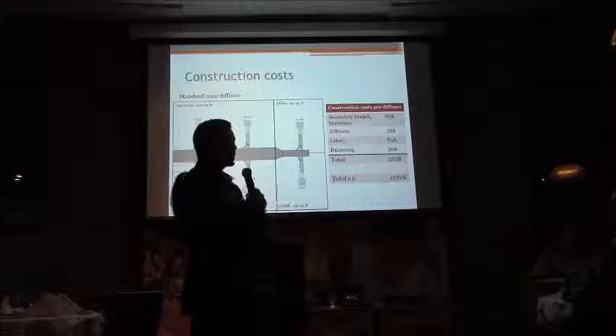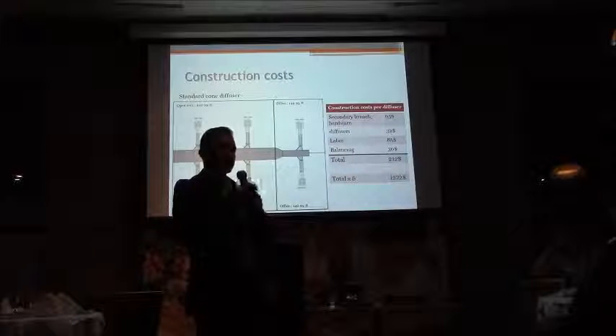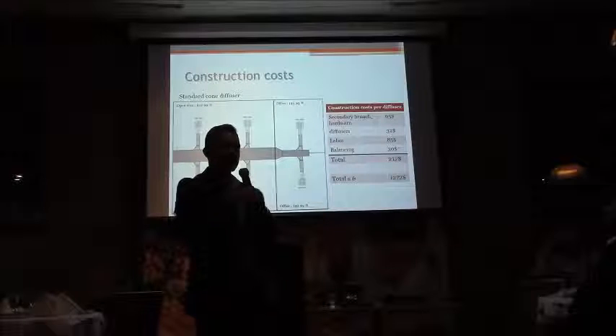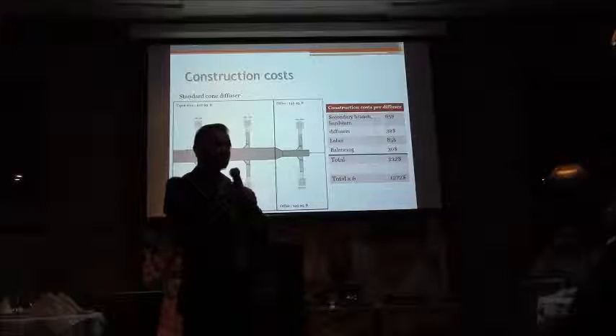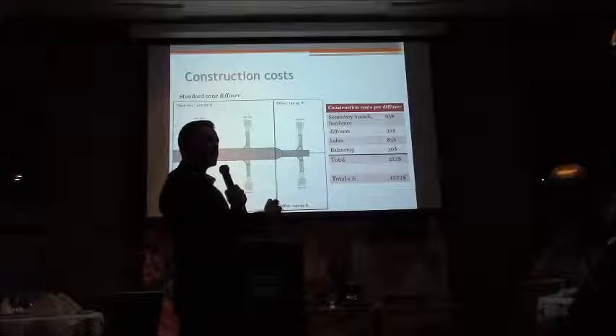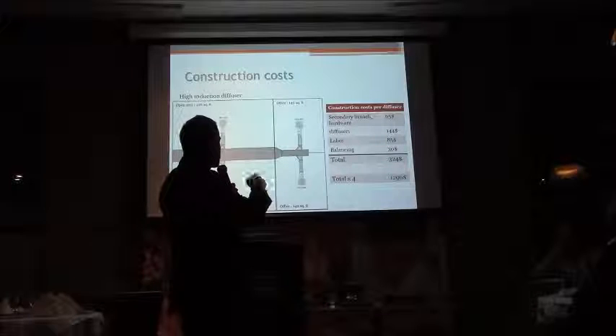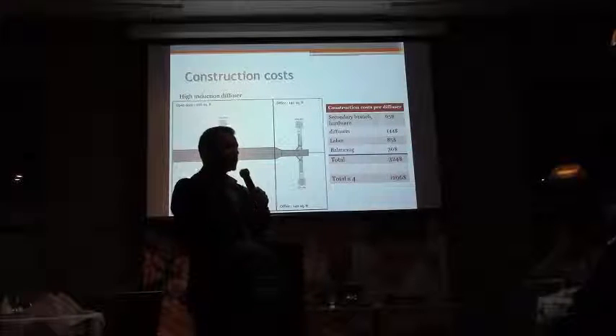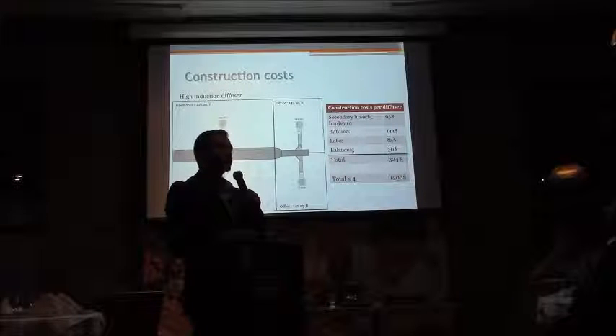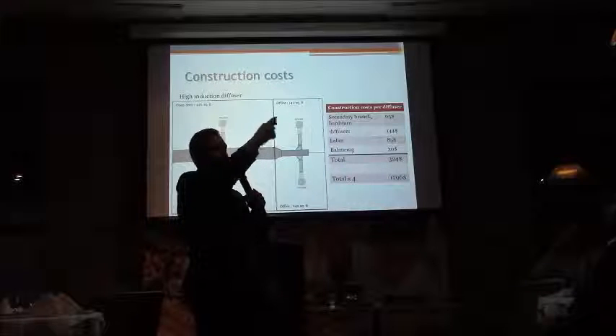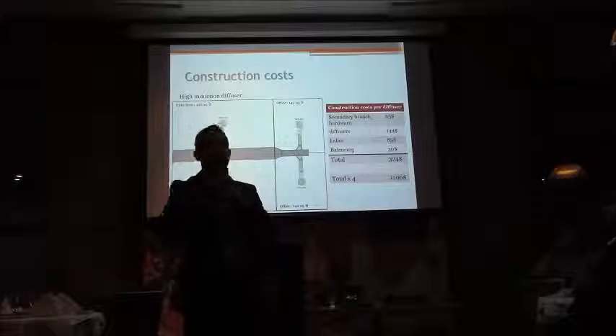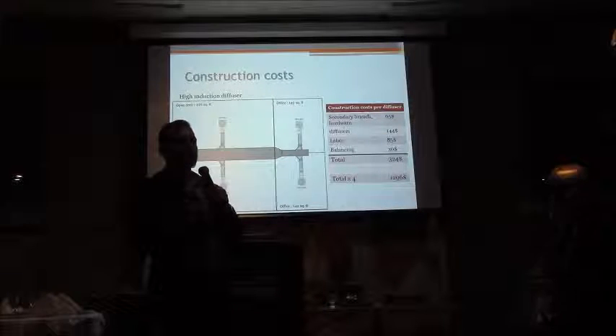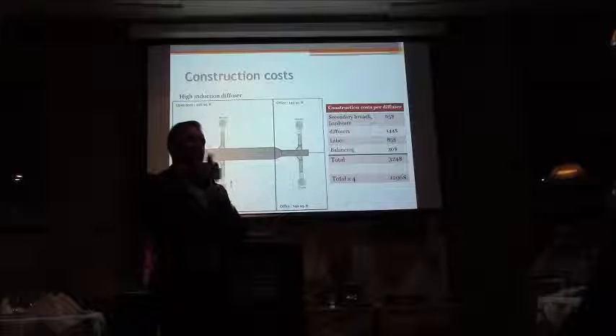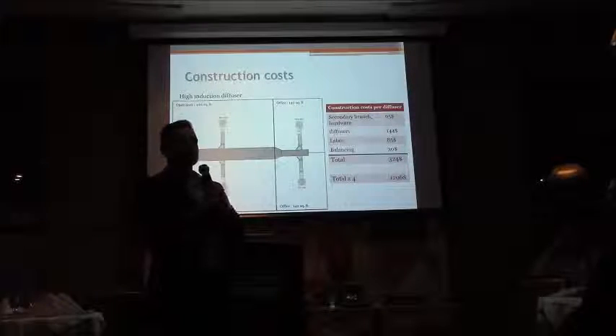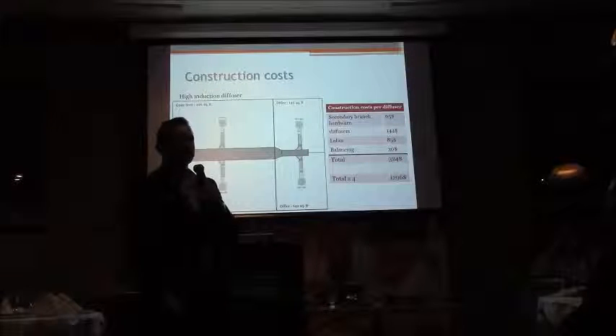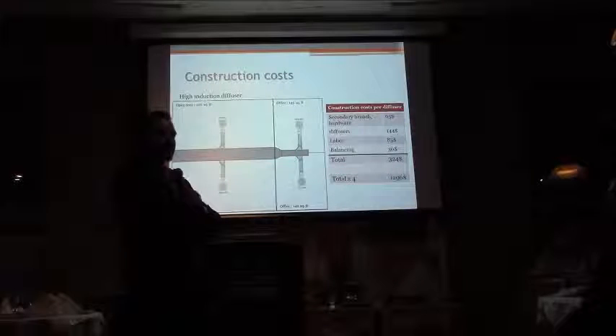Exactly. If you have a plenum, you're able to eliminate all those field realities, the flexible connection, the added sound. Because of that, you're able to throw more air per diffuser. You can go up to 400 CFMs per diffuser. I limited my example to 280. But with high induction, I've seen a lot of applications where they go up to 400 CFMs per diffuser. So if each of these diffusers is at 200 CFMs, then we could reduce the amount of diffusers by half. They're more expensive to buy, but you get fewer diffusers to install, fewer diffusers to balance, fewer secondary branches and less hardware. Right, but you're still assured that you have adequate distribution to the perimeter areas.